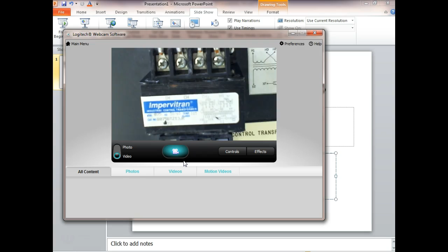If I was going from 120 volts, and it's very popular now to use 24 volts as a control voltage, I would use a step-down transformer. We had two robots in the hall building that run off 440, and we don't have any 440 over there—the highest we have is 240. So what do we have to do? We have to use step-up transformers. But normally, this transformer could either step up or step down.